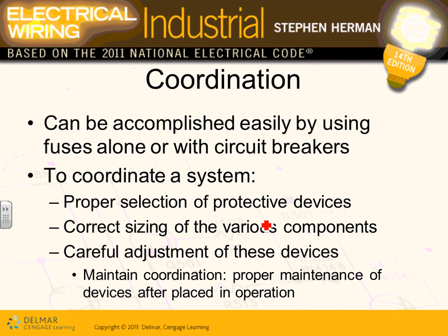This is probably the second time we've talked about the current characteristic curve. In a couple of weeks, you're going to hear your friend Chad standing here and using SKM PTW to do this coordination. When you do overcurrent coordination, if Karen were to go right now and short one of these lights above your head, you want the circuit breaker in this panel right in this room to trip, not the main 3,000 amp fuse in the basement. That's what coordination is.